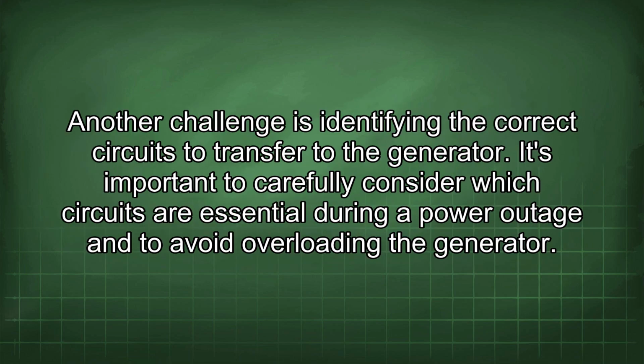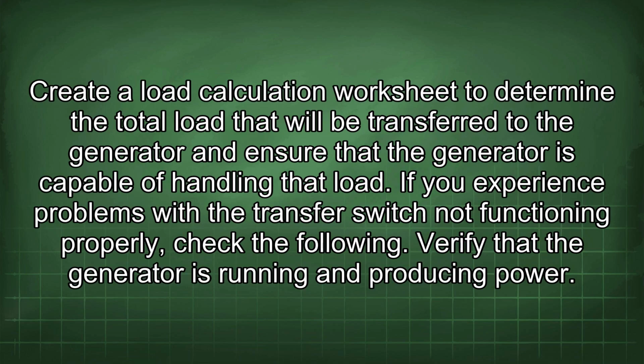Another challenge is identifying the correct circuits to transfer to the generator. It's important to carefully consider which circuits are essential during a power outage and to avoid overloading the generator. Create a load calculation worksheet to determine the total load that will be transferred to the generator and ensure that the generator is capable of handling that load.